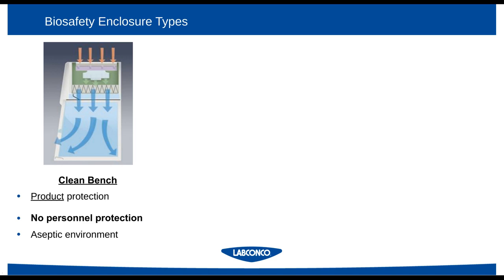As Simon was saying, there are a handful of different opportunities for containment out there. In the form of Labconco's products, those are the next three that'll be displayed on this slide. It involves, most simply, a clean bench or a laminar airflow hood. This is a downflow. Sometimes they exist in horizontal flow designs, and many liquid handler instruments out there have options for these to be purchased fully integrated. It's worth mentioning, however, that the only protection that is provided by this type of enclosure is product protection or sample protection. So while you can achieve the elimination of cross-contamination and room contamination of your samples, there's no protection for users.